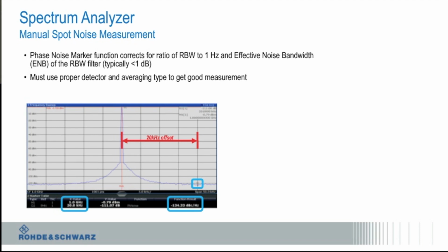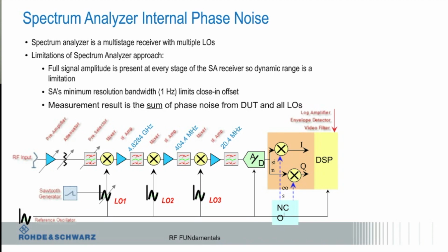Okay, so somebody just asked me about a spectrum analyzer. This is very roughly the architecture of an FSW. There's multiple down conversions depending on frequency or where you're going or what you're doing with the signal. But you can see here there's more than one LO, right?